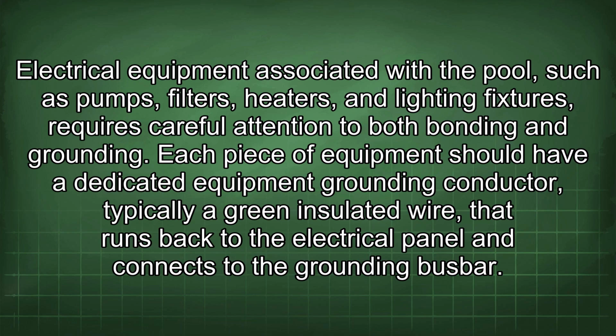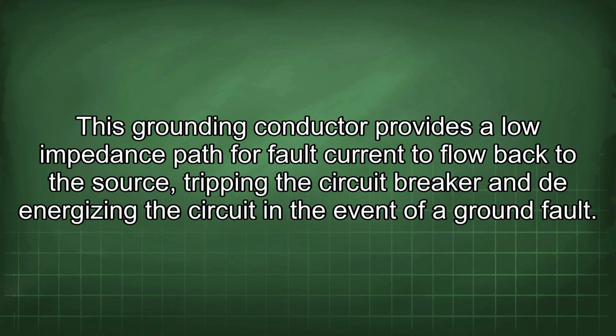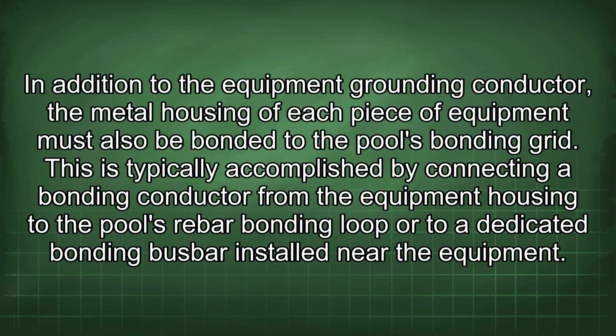Electrical equipment associated with the pool, such as pumps, filters, heaters, and lighting fixtures, requires careful attention to both bonding and grounding. Each piece of equipment should have a dedicated equipment grounding conductor, typically a green insulated wire that runs back to the electrical panel and connects to the grounding bus bar. This grounding conductor provides a low impedance path for fault current to flow back to the source, tripping the circuit breaker and de-energizing the circuit in the event of a ground fault. In addition to the equipment grounding conductor, the metal housing of each piece of equipment must also be bonded to the pool's bonding grid. This is typically accomplished by connecting a bonding conductor from the equipment housing to the pool's rebar bonding loop or to a dedicated bonding busbar installed near the equipment.